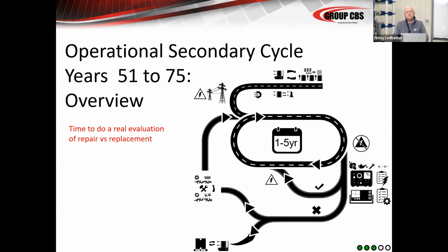Now, the equipment that stays in service over this 25 years is probably going to stay in service another 25 years. The equipment that you replace now is equipment that's going to start its life cycle over again with modern equipment. That equipment might have more modern insulation, more modern controls, more modern breakers, but they won't be as robust as the ones you'll be getting rid of. Their actual life cycle will be less. The circuit breakers you get today, the vacuum interrupters you get today, will not live as long as the ones that were created 30, 40, 50 years ago. So don't expect them to. The switchgear might, though, because insulation materials, controls, instrument transformers, some of that stuff has become more robust.